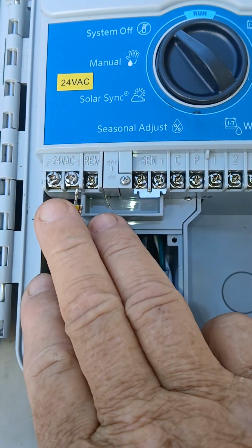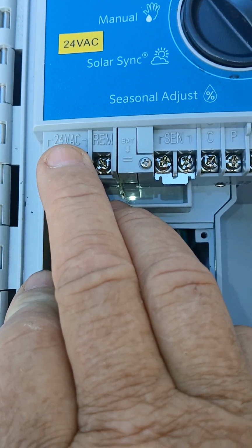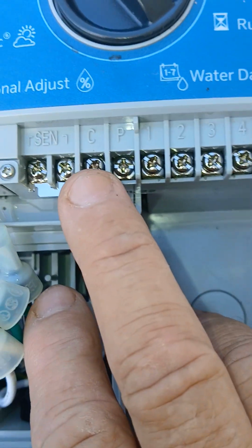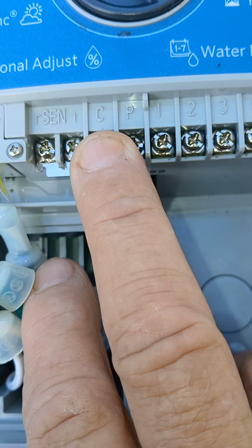So, but again, okay, step 1, we have a control box. Step 2, we have power. Step 3, there must be a transformer to get it down to 24 volts. Step 4, we have a common wire. This common wire must be attached to every valve, normally it is the white wire. And then the hot wires are the ones for each zone.